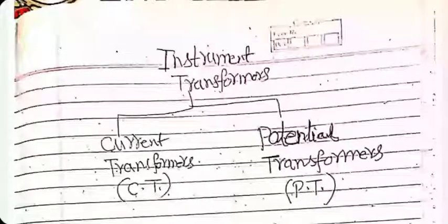If the voltage to be measured is say 33 kilovolt, no voltmeter would be able to handle it. It will burn. So we reduce that 33 kilovolt to a more practical value, let's say 1000 volt or 500 volt, by using a potential transformer, and then do the measurement and then make the correction, because we know the turns ratio of the transformer.